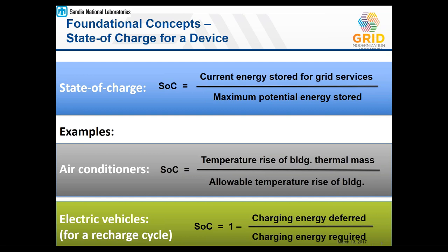Similarly, with electric vehicles, you plug it in at, say, 10 o'clock, you need it charged all the way to 100% by 6 o'clock, but you really don't care when and how the battery charges in that window. You can abstract out the deferred charge divided by the charging energy required as this metric for state of charge. And in this way, you can take a step back and really look at these technologies on an even basis, because whether you have 50% state of charge in a battery or 50% state of charge in 1,000 air conditioners spread out over an area, it really doesn't matter to the grid service.